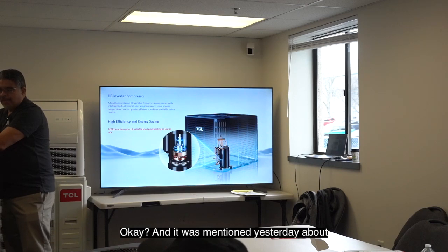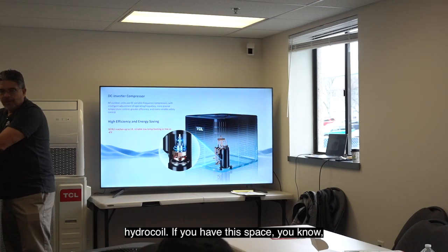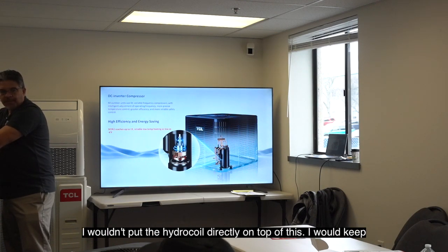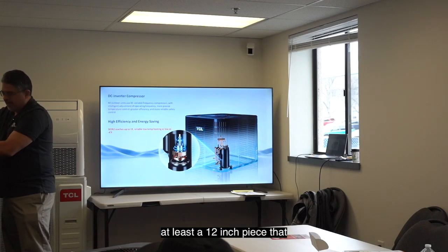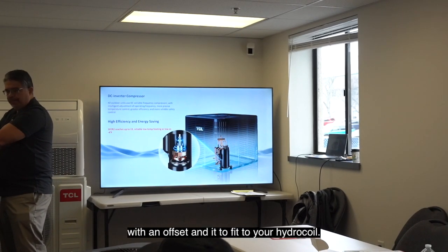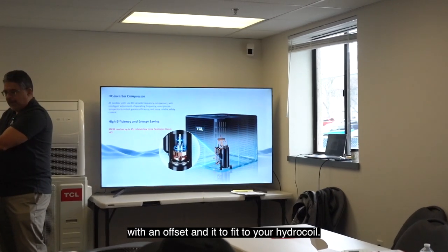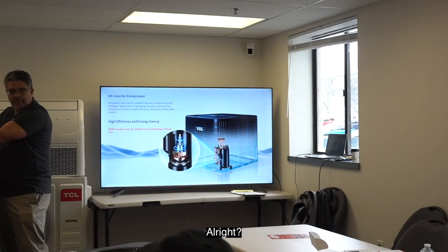Okay, and it was mentioned yesterday about the hydro coil. If you have the space, I wouldn't put the hydro coil directly on top of this. I would keep at least a 12-inch piece with an offset, and fit it to your hydro coil.